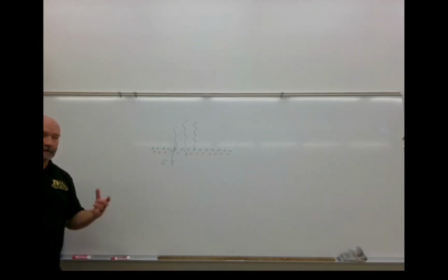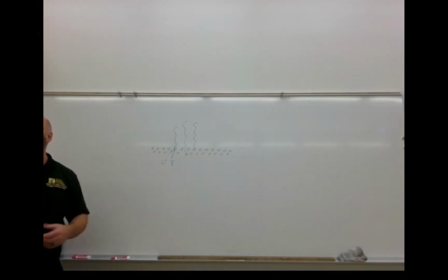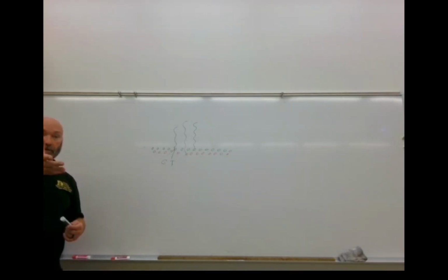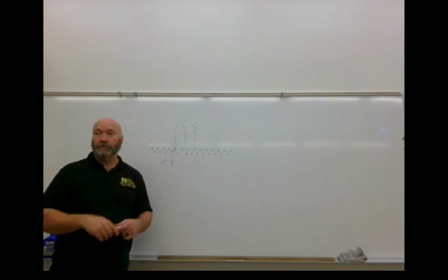So once we get up to about the knee size, 10 centimeters, shoulder size, 10 centimeters, and above, we're going to be creating so much scatter radiation that we really need to do something with it. What's that? Did you say grid? Yeah. Yes, grid. We're going to use grid.